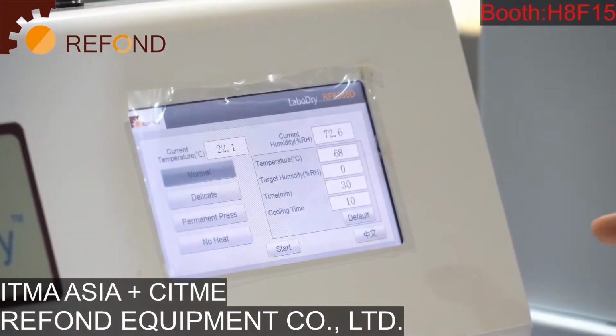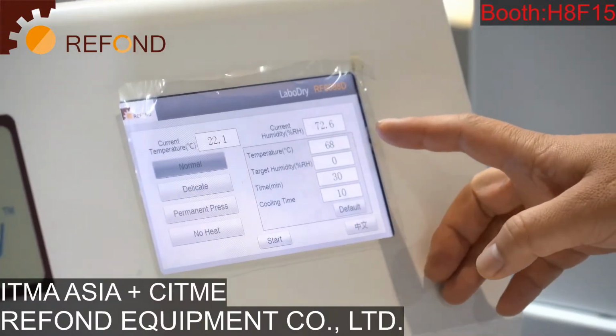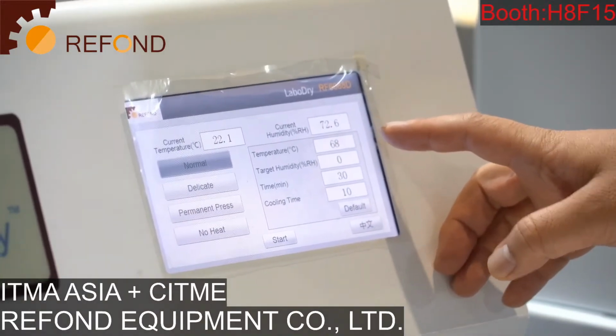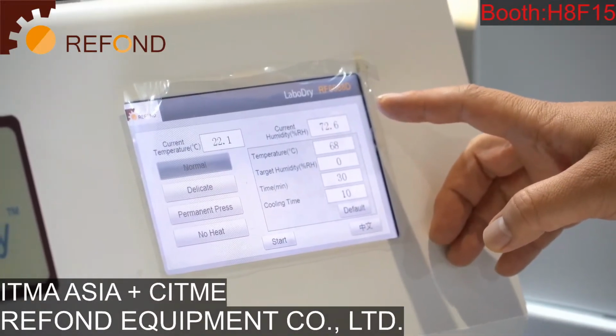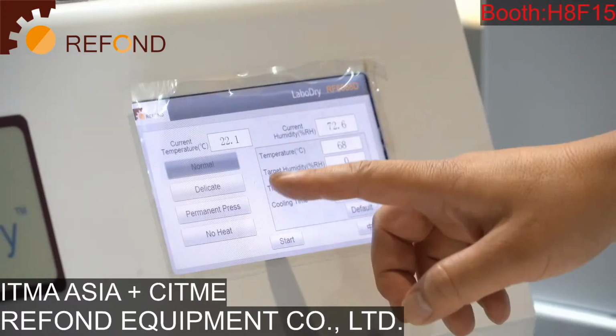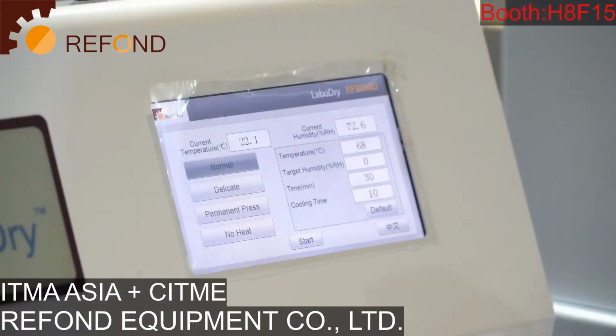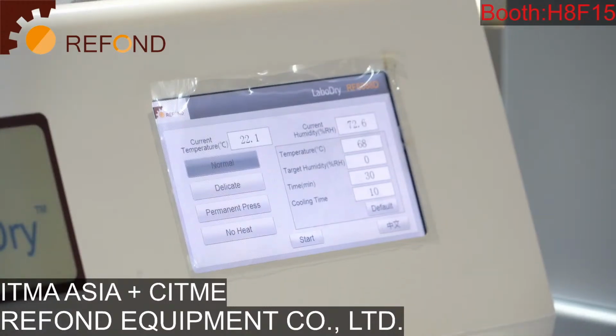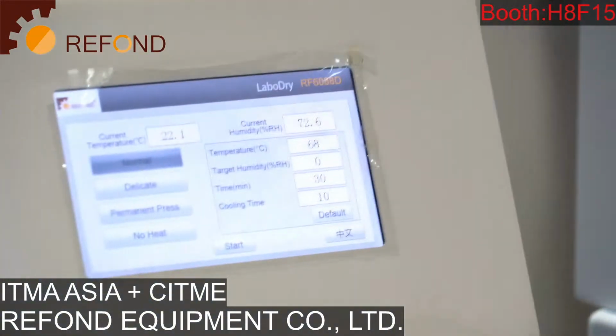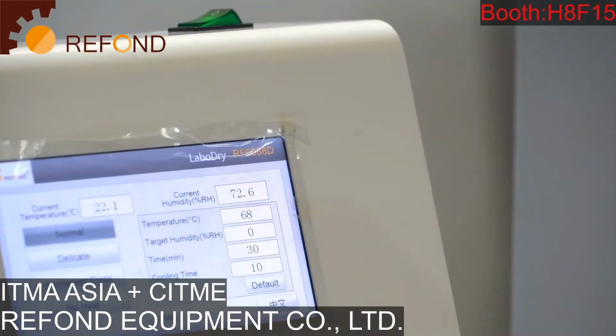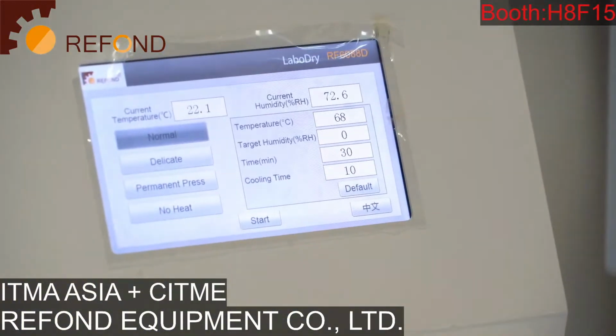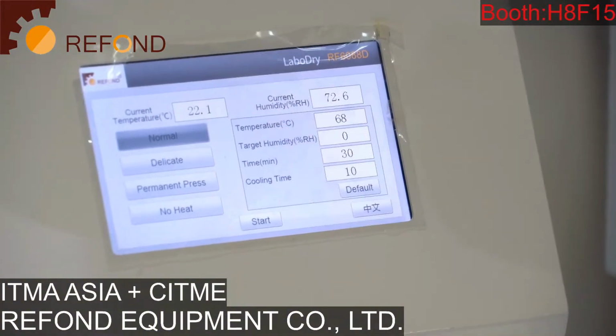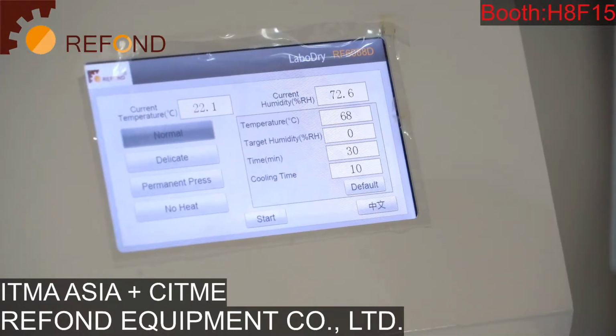And the temperature is automatic control. In addition, we have set another function in our LaboDry drying machines. What's the new function? We have built in a humidity sensor inside the exhaust pipeline to monitor the humidity of the exhausted air.